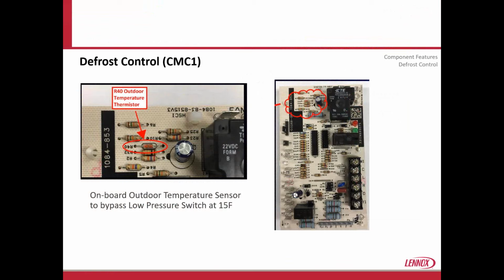It's done in a safe manner, because just like low ambient cooling, where we control the outdoor fan motor and the head pressure, it's really not even important anymore. There's really no damage that can be caused from it. So anything below 15 degrees, the board is automatically going to no longer look at the low pressure switch. So if you're running a really cool, really low pressure heat pump, which is not uncommon, understand our equipment is installed all the way up in Canada too, so it gets extremely cold in some climates where this equipment is running.